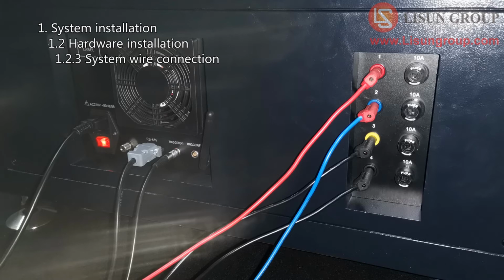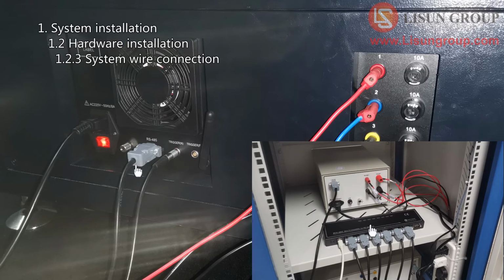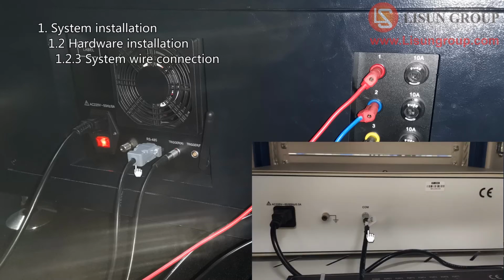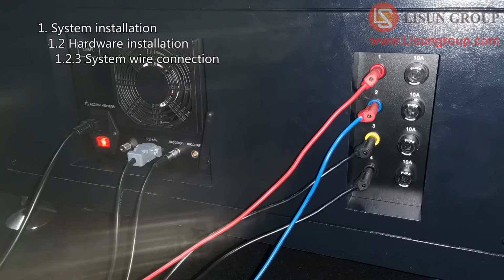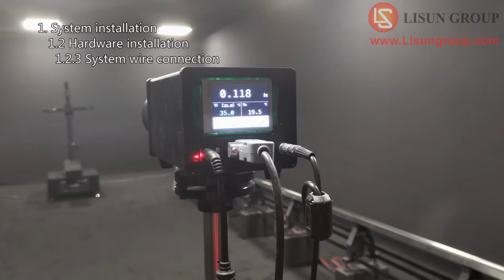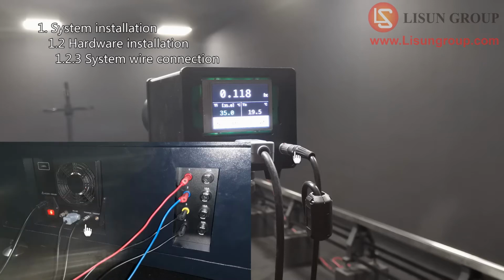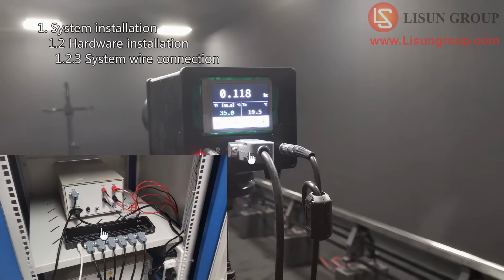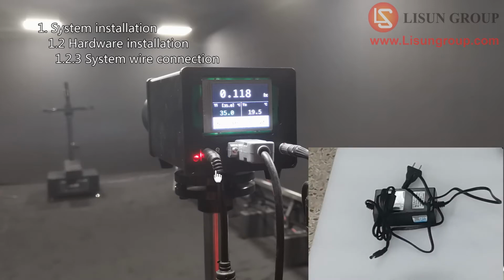There is a 1-to-2 communication cable for the goniophotometer. Connect the RS-485 port at one end to the goniophotometer. The other end splits in two. Connect the end with RS-485 port to the communication box inside of the cabinet. Connect the other end to the rotary actuator controller inside of the cabinet. If there is only one photodetector in your system, connect it to trigger IN, with the signal line. There are 3 wires connected to the photodetector. The signal line is from the goniophotometer. The communication cable is connected to the communication box inside of the cabinet. The last one is the power adapter.